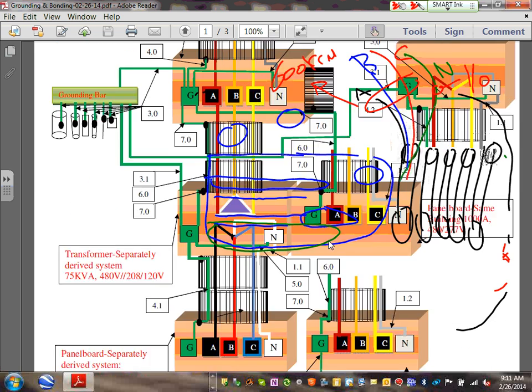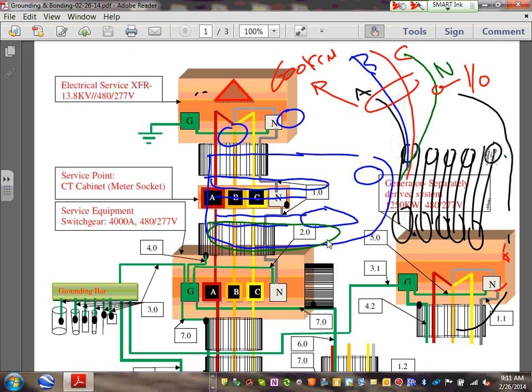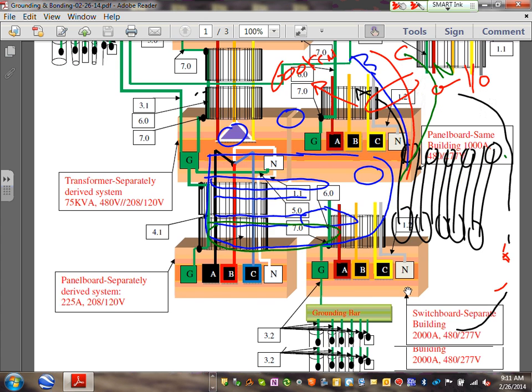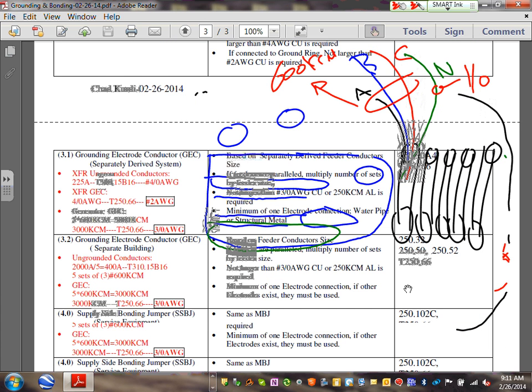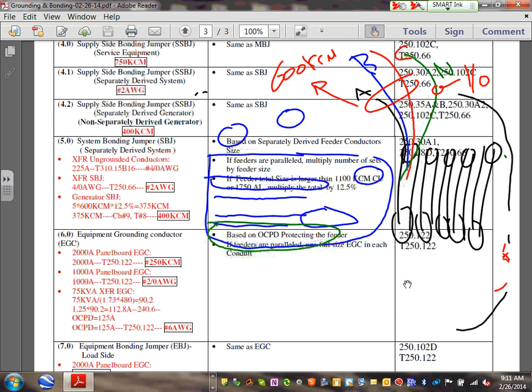I'm going to go back, and at the generator, the second thing I'm going to size is number 5. Can you guys see 5.0? 5.0 right here, that wire is called the system bonding jumper. So let's go to 5.0. Gentlemen, here you go, 5.0 right here.